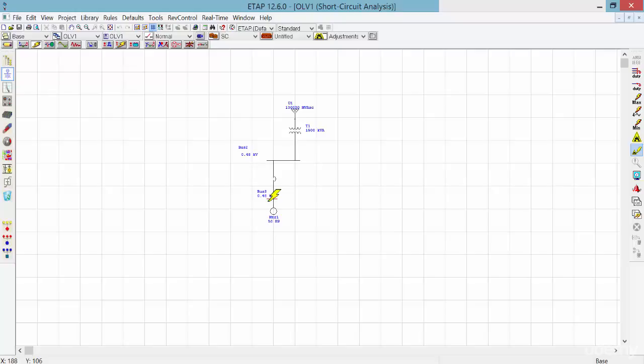That's when you can just click your mouse and ETAP would show you that the next protective device that would trip would be this circuit breaker, and it also gives you the fault clearing time of this incident, which was 13 milliseconds as you remember, and the incident amperage regarding this fault would be 19.44 kiloamps.